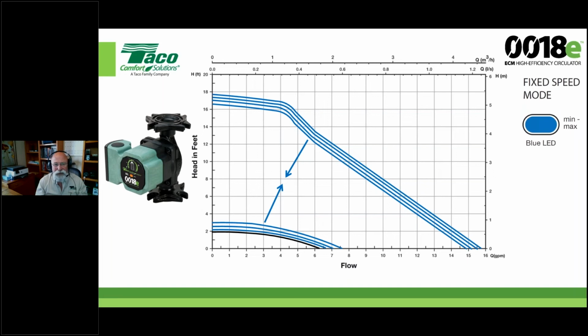Okay, that's what's cool about this pump. And a lot of our competition can't do that. They're still giving you 3 speeds under that fixed mode of operation. So again, we have just a dial on the pump that you can think of like a volume dial on a radio or a dimmer switch. We can turn it all the way low, which is 4 watts. All the way up on this pump is 44 watts. But what's more important and more popular is the fact that we can put it anywhere between those two that's appropriate for that job. In this case, let's take a look at it.